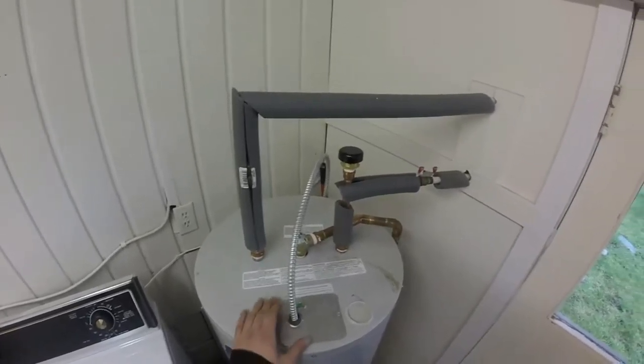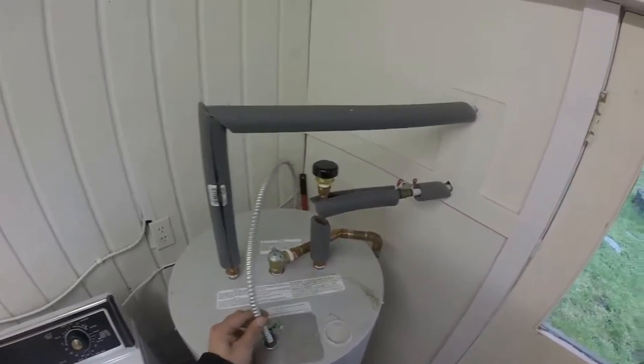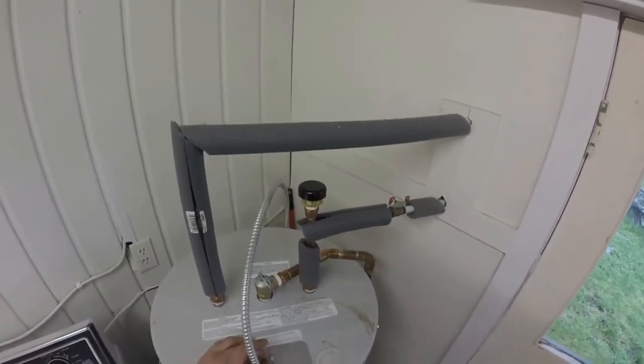You want to check for corrosion around the fittings. Make sure there's no corrosion here, no water sitting here. Same with the electrical. You want to make sure there's no water or corrosion around the electrical. Make sure everything is tight and grounded properly.